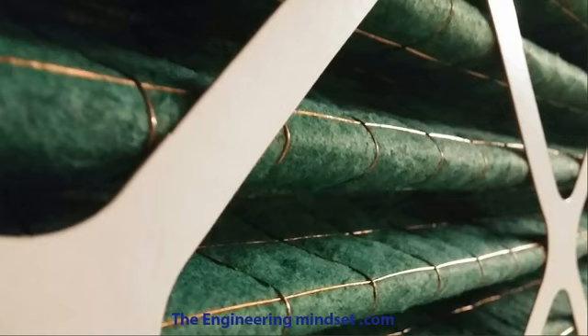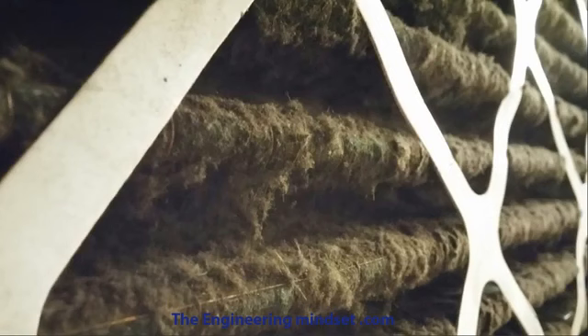So this is a close-up of the filter material there, and these primary filters, they're pretty effective at catching dust particles down to around 4 or 5 microns, but they can't really catch anything less than say 1 or 2 microns. Now this is a dirty filter, as you can see, it's absolutely covered in dust, and this has taken a few months to build up to this level, but that does depend on where your air intake is located and where your building is located. If you're in some busy industrial unit, then obviously it's going to be probably a lot more dust than say if your building intake was near the seaside.